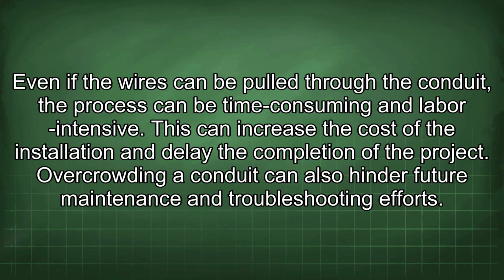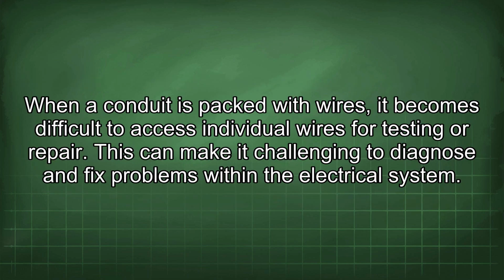Even if the wires can be pulled through the conduit, the process can be time-consuming and labor-intensive. This can increase the cost of the installation and delay the completion of the project. Overcrowding a conduit can also hinder future maintenance and troubleshooting efforts. When a conduit is packed with wires, it becomes difficult to access individual wires for testing or repair. This can make it challenging to diagnose and fix problems within the electrical system.